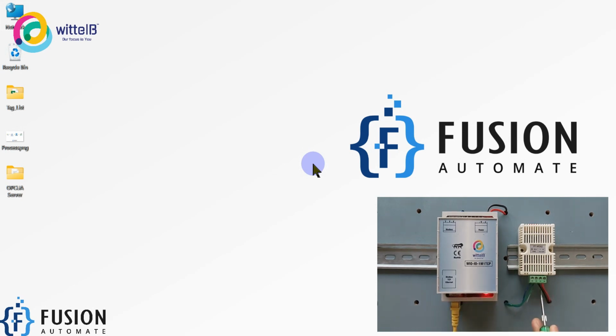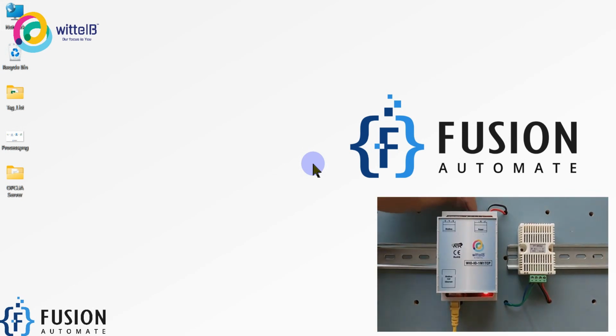I have connected the power supply cable, you can see red and black. Here also you can see the red and black, and here we have this green and blue cable for serial connection. The serial connection of this device goes to this gateway, and this gateway is converting Modbus serial data into Modbus TCP. You can see this LAN cable is connected to my system, so we can read the Modbus serial data via Modbus TCP communication.